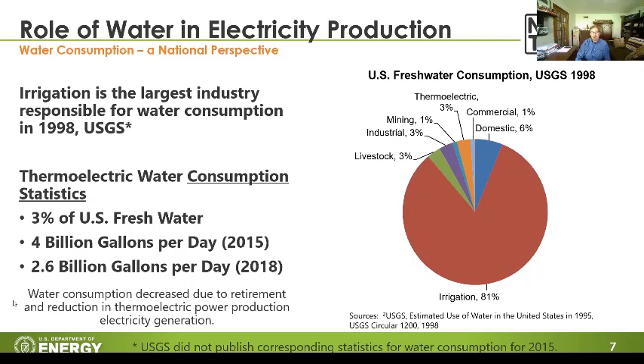So how is water really used in a power plant? Water is heated in the boiler to produce steam that turns a turbine and generator to produce electricity. After generation, the steam is condensed using a separate cooling water stream. That cooling water stream is either directly discharged back to the source body of water, called once-through cooling, or recycled to lower the water temperature and improve heat transfer.